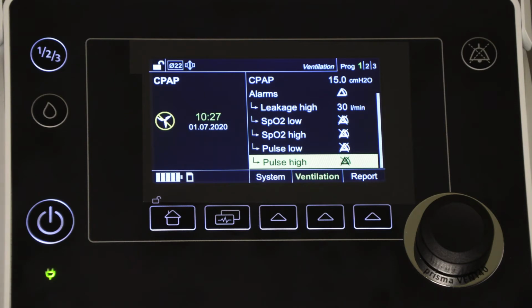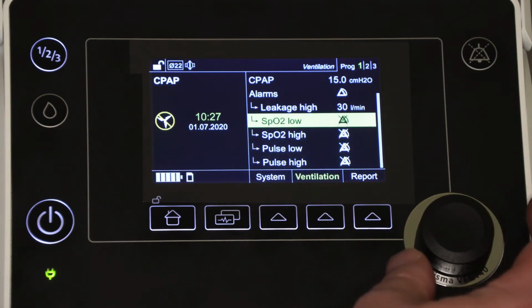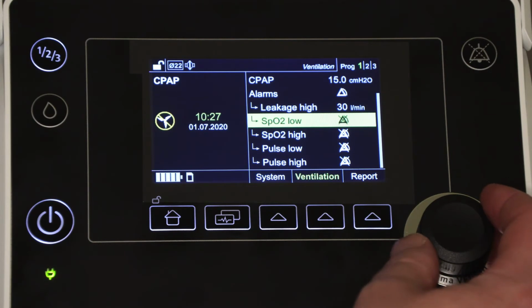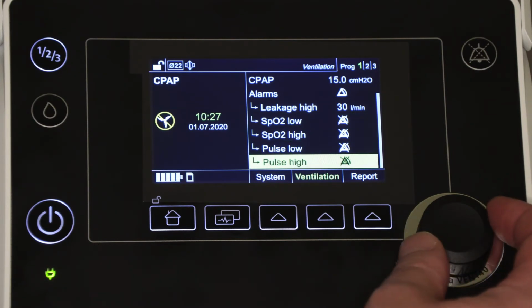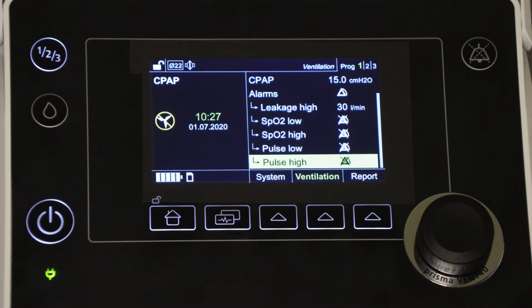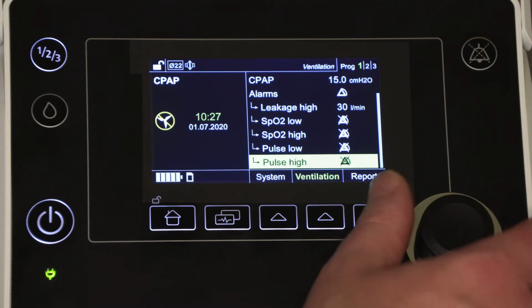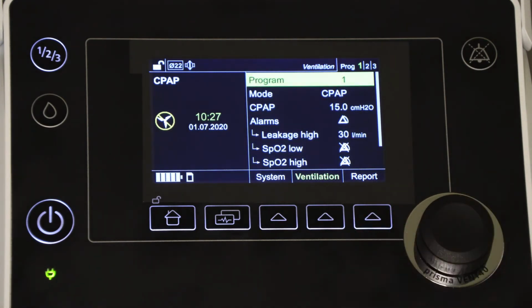The rest of the alarm settings available in this therapy mode are only of use if you're using prismaVENT's optional SpO2 module. You can adjust alarm parameters for SpO2 low and high and pulse low and high. However, if you're not using the SpO2 module, you can leave these alarm values set to off and you're done. All you need to do now is connect the patient to the breathing tube and start therapy.